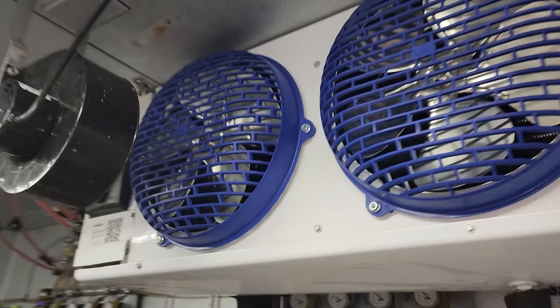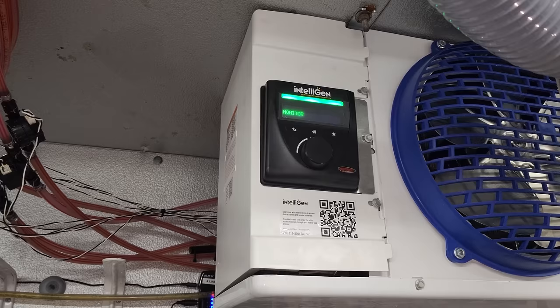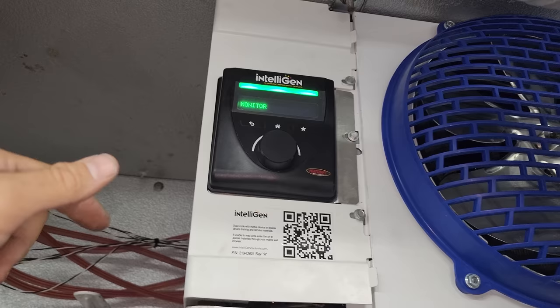As far as the IntelliGen evaporator goes, it's just a smart controller. The biggest piece of advice I can give you if you're installing an IntelliGen system, a Beacon system, or a QRC system: braze with nitrogen and follow the instructions. Don't over-pressurize the system when you're doing nitrogen pressure tests and different things. Trust me, I've made those mistakes and ruined pressure transducers.